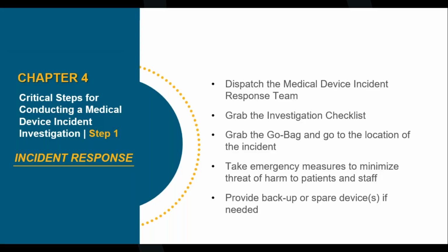So we're going to step through the critical steps of an incident investigation. Step 1 is incident response. So you get a call, something happened. Hopefully it just happened while you're there, and it's not a night or weekend, but often that is the case where we find out about something much later. But in any event, when you get the call that something has happened with a medical device, an event has occurred that is untoward, we want to dispatch the medical device incident response team, grab your incident checklist, which we'll go through here in a minute, and your go bag, which we'll talk about in a minute as well.